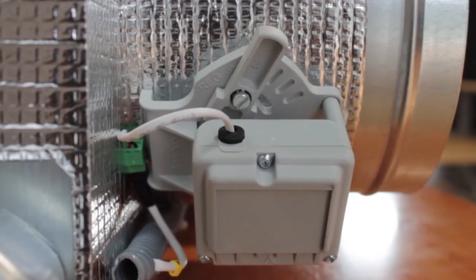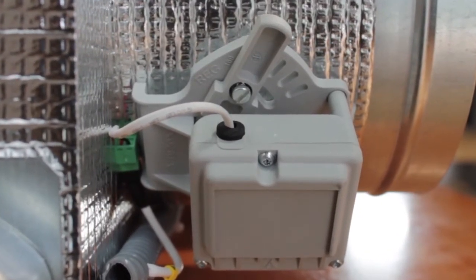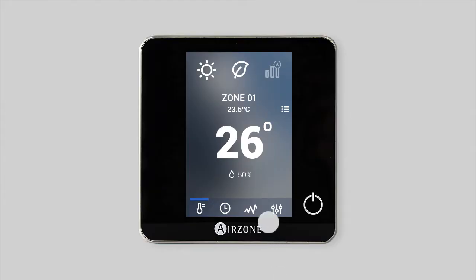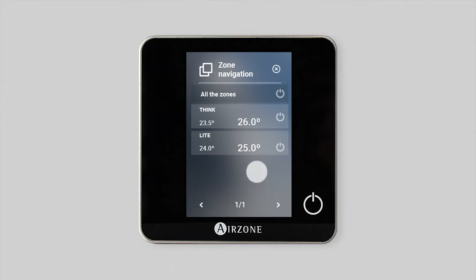To balance the airflow, repeat these steps: put all the zones on demand and use an anemometer to measure the airflow at all outputs.